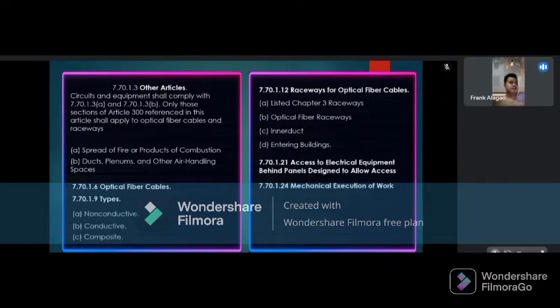Letter D is entering buildings. So next is yung Article 7.70.1.21, access to electrical equipment behind panels designed to allow access. Access to electrical equipment shall not be denied by accumulation of cables that prevents removal of panels, including suspended ceiling panels.